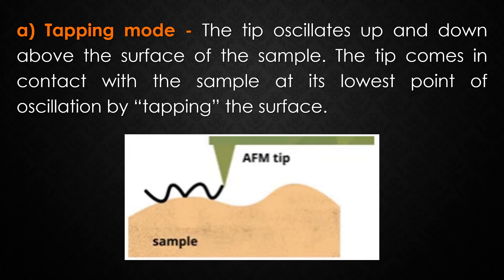In tapping mode the tip oscillates up and down above the surface of the sample. The tip comes in contact with the sample at its lowest point of oscillation by tapping the surface of the sample. The repulsive forces are detected when the tip taps the surface while attractive forces are detected at the peak of oscillation. The tapping mode generally lessens the damage done to the surface and the tip compared to the contact mode. This technique is used to image the formation of molecules in chemistry among many other applications.